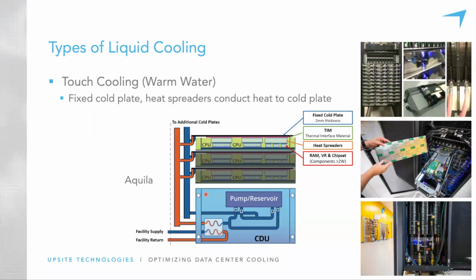And this is a solution that was developed by our parent company, Aquila. This solution involves manifolds that are at the back of the cabinet, and they are permanently affixed to cold plates that have the liquid flowing through them. So there are no connectors in this solution. This is all manufactured ahead of time and pressure tested, and there's no need to ever disconnect or reconnect any of these fittings. It's all a permanent fixed solution.